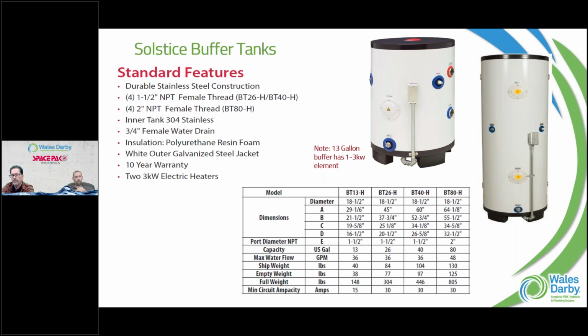So we offer this in 4 different sizes, the 13, 26, 40, and 80. Everything but the 13 has dual elements in it. So the 13-gallon has 1 3 kW element in it, where our larger systems come with dual. Those elements would be used, again, as a boost feature. We need to bump that temperature up a little bit, we're going to throw some quick BTUs. If you did the math, Anthony, I'll put you on the spot, the 2 3 kW, so 6 kW. How much heat are we getting out of that? About 20,000 plus, 22,000. So over 20,000 BTUs. Yeah, it's a good little dump.